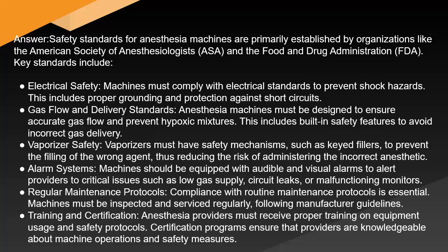Gas flow and delivery standards. Anesthesia machines must be designed to ensure accurate gas flow and prevent hypoxic mixtures. This includes built-in safety features to avoid incorrect gas delivery. Vaporizer safety. Vaporizers must have safety mechanisms such as keyed fillers to prevent the filling of the wrong agent, thus reducing the risk of administering the incorrect anesthetic. Alarm systems. Machines should be equipped with audible and visual alarms to alert providers to critical issues such as low gas supply, circuit leaks, or malfunctioning monitors.